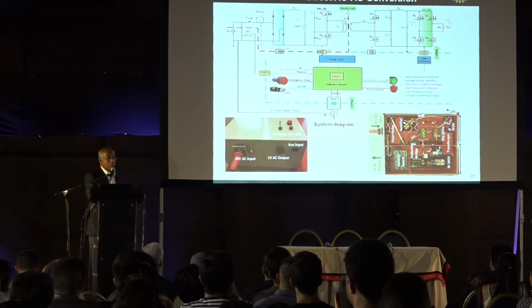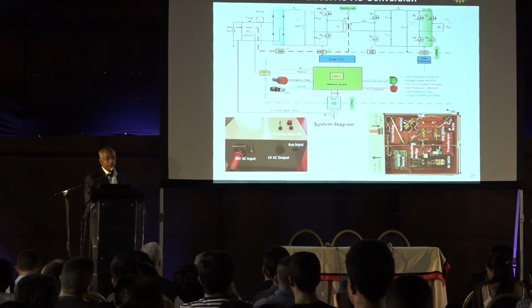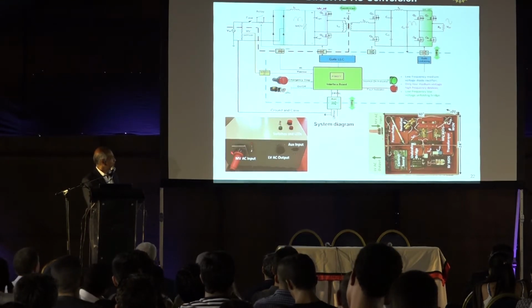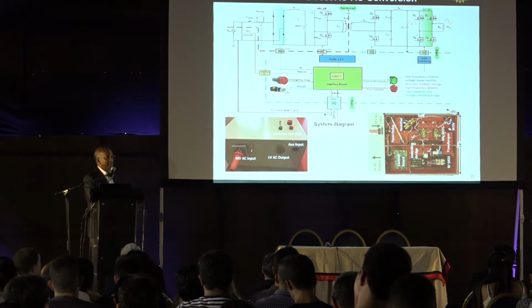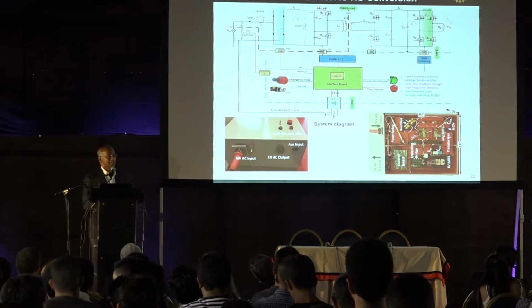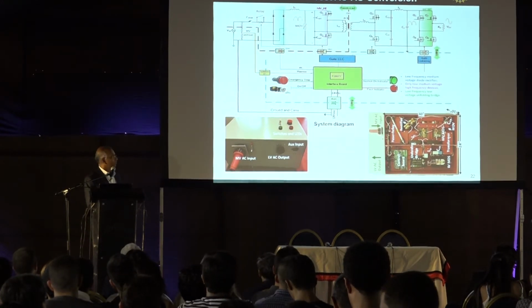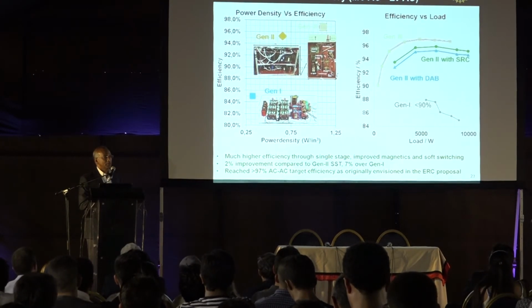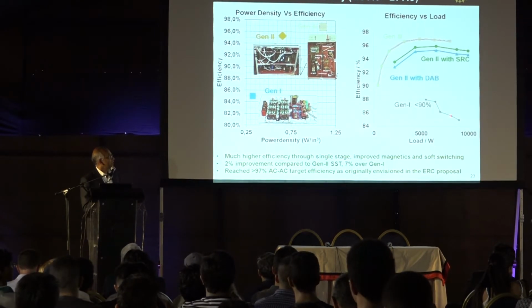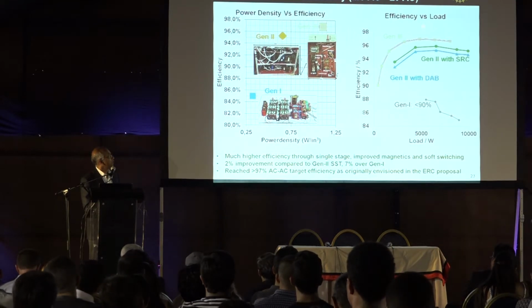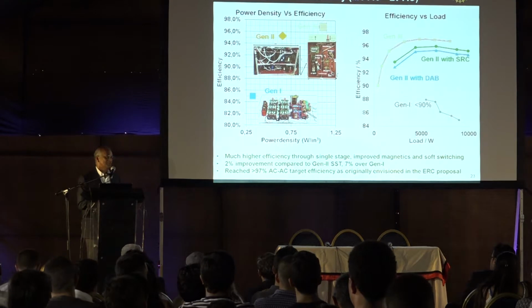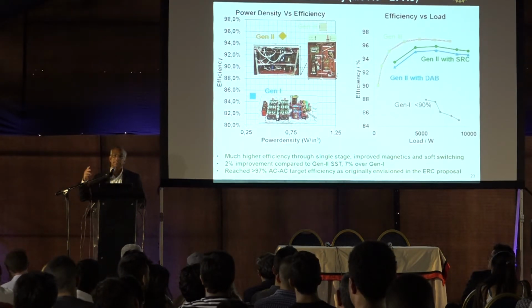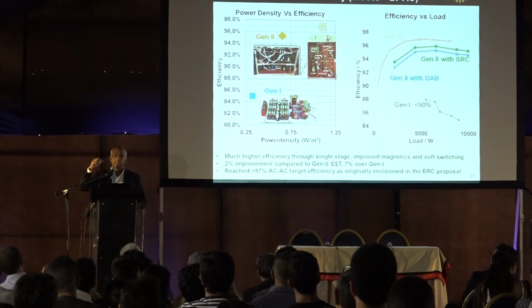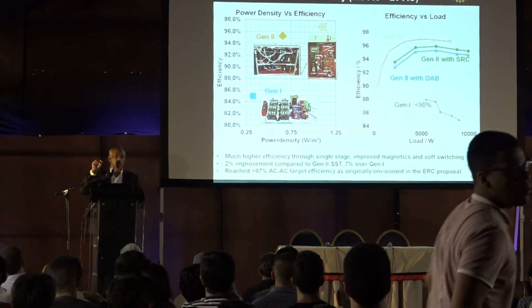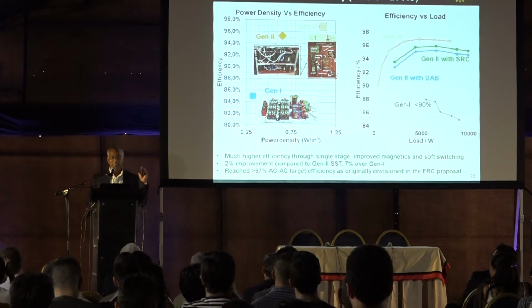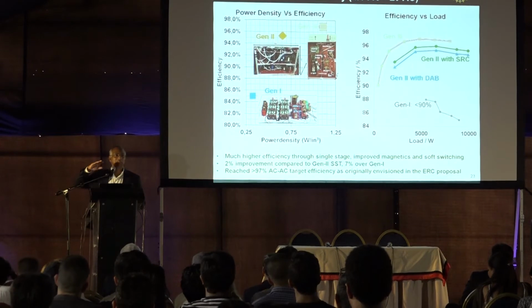So in our center, we have developed up to third generations of these solid-state transformers. This is another improved version of that, and this is showing how it's enclosed in a box, just to replicate from an AC input to an AC output a traditional transformer that is ready to be installed. So going one more step, showing the efficiencies that can be achieved, these are experimental results that we have, where gradually from generation 1 with 90% efficiency, we have moved up to about 97% efficiency of these transformers. So one key difference with traditional transformers is that traditional transformers are designed to have their peak efficiency at the maximum load level. It is very inefficient at light load conditions. But these electronic-based transformers can be made to be efficient from light load to full load conditions.